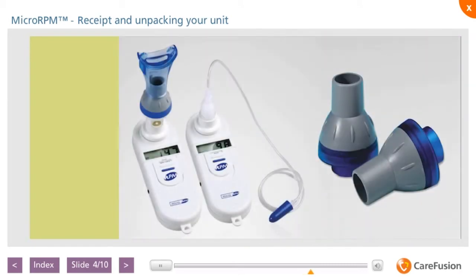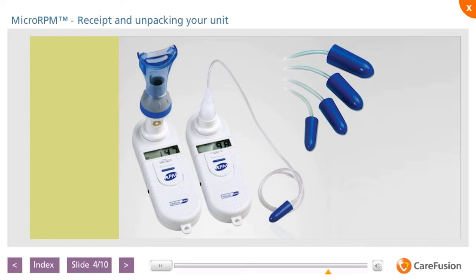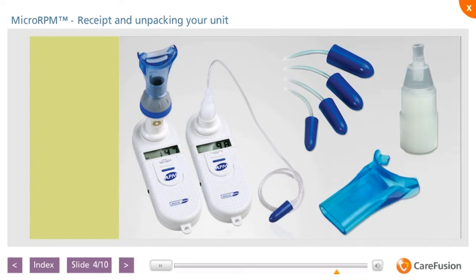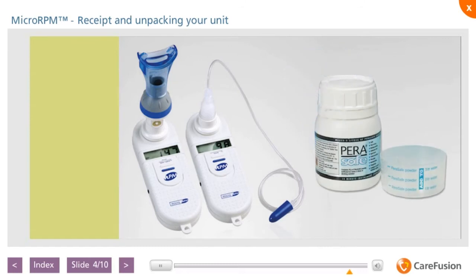The pulmonary filters are for single patient use only and should be disposed of once testing is complete. The nasal olives, nasal probe adapter and flanged mouthpiece are also for single patient use and should be cleaned using a detergent and then cold sterilized. CareFusion recommend the use of PeraSafe or Descogen. And note here that the nasal probes can't be autoclaved.